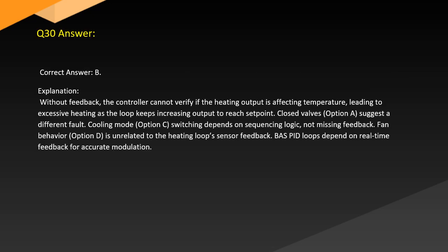Answer. Correct answer: B. Explanation. Without feedback, the controller cannot verify if the heating output is affecting temperature, leading to excessive heating as the loop keeps increasing output to reach set point. Closed valves, option A, suggest a different fault. Cooling mode, option C, switching depends on sequencing logic, not missing feedback. Fan behavior, option D, is unrelated to the heating loop sensor feedback. BAS PID loops depend on real feedback for accurate modulation.